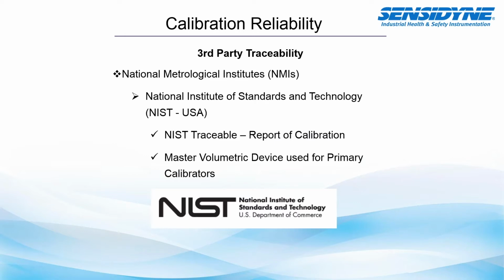So third-party traceability is typically done by a National Metrological Institute. In the case of the United States, we use NIST, which is the National Institute of Standards and Technology. They are pretty much the forebearers of what a standard unit of measurement is for consistency purposes all across the nation. And of course, NIST works with other institutes around the world to make sure when we say a cubic centimeter is a cubic centimeter, it's measured as a cubic centimeter the same everywhere. They are also the holders of the master volumetric devices used for primary calibrators.